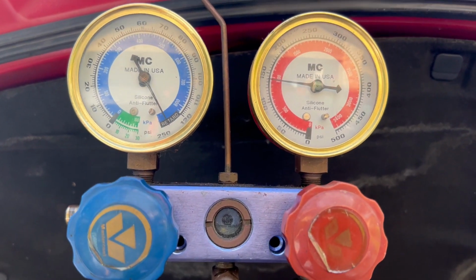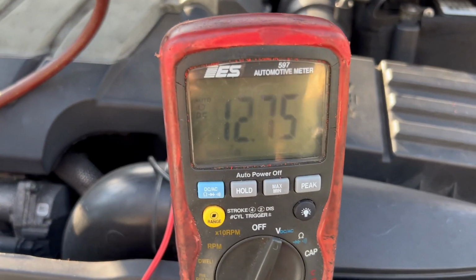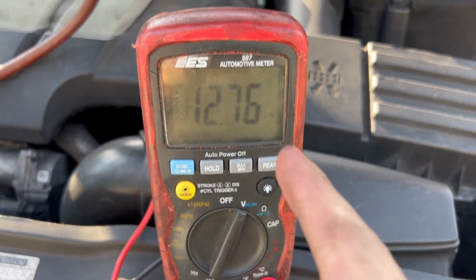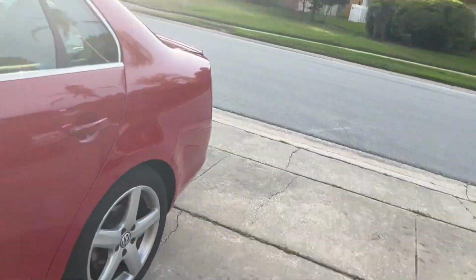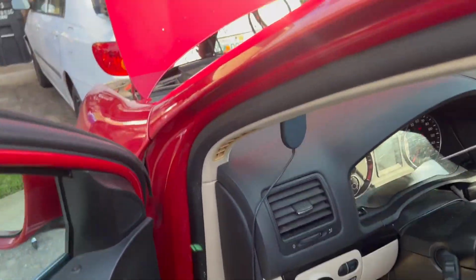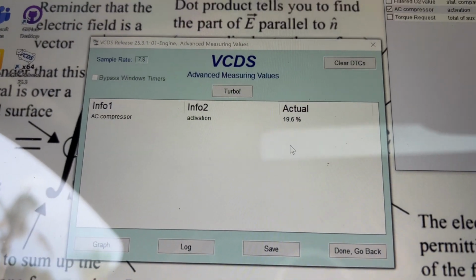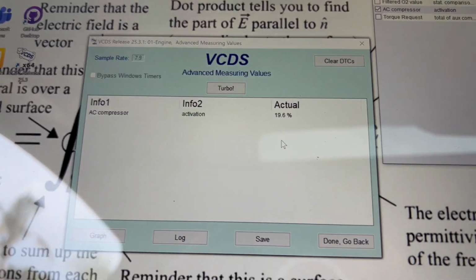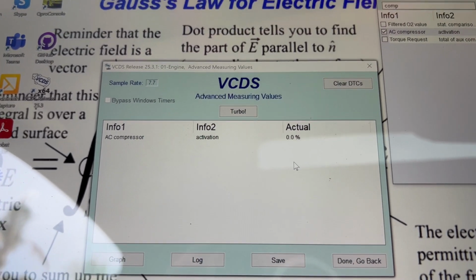So not only is the compressor commanding, according to our voltage on the meter here, it's commanding the valve on. Also, according to our ECM, it is also commanding the valve to turn on as well. And if I turn the AC off, it goes to 0.